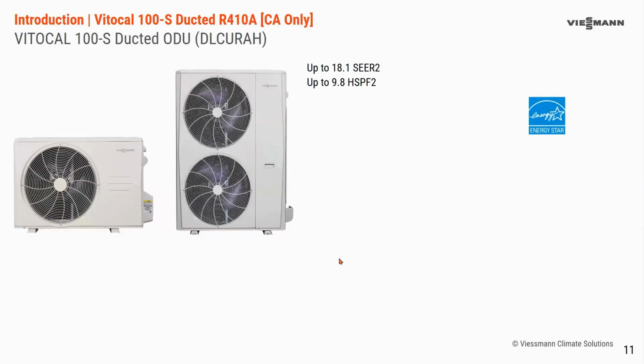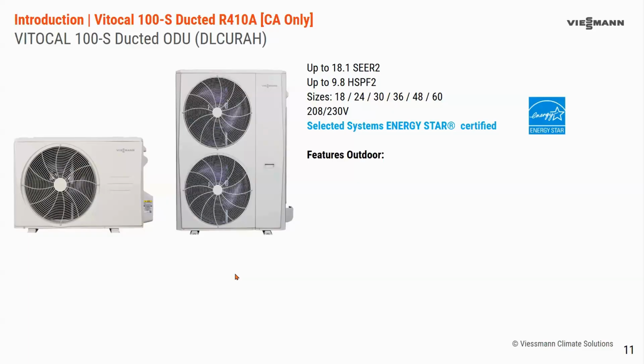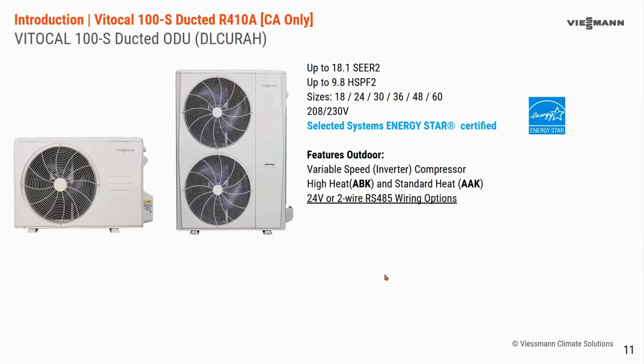The outdoor units themselves are visually almost identical to the ductless units, with the difference being some of the hardware in the connection points. So 18 to 60,000 BTU. These are all 208/230. Variable speed compressor, so you still have that technology. We have high heat and standard heat models. A big difference on this outdoor unit is that you have the ability to wire to the indoor unit with either 24 volt or the 2-wire RS485 connection.